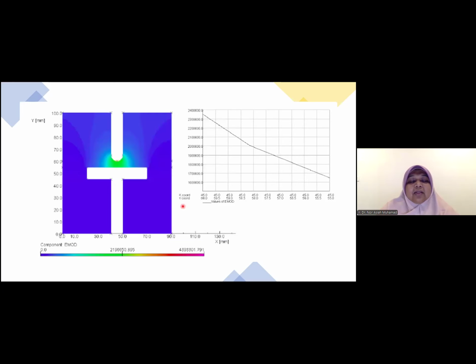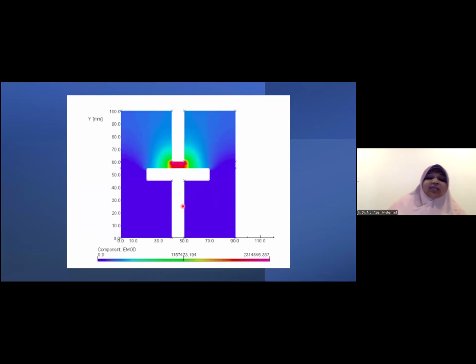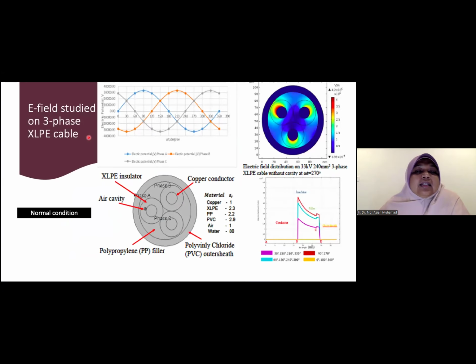So here is some example to study the E-field. We study the E-field for the XLPE cable. Here the study is to see what happens if we have manufacturing defects, because it involves the insulating material, which is a polymer. In the process for the polymer to be hardened and shaped into the shape that we want, sometimes there are air cavities or also water cavities trapped inside. And this water cavity inside the cable will affect the E-field.